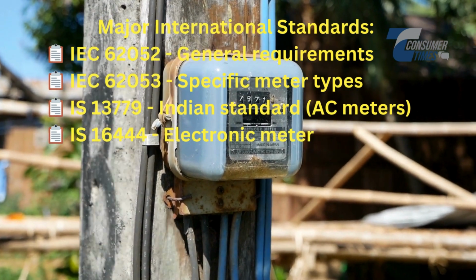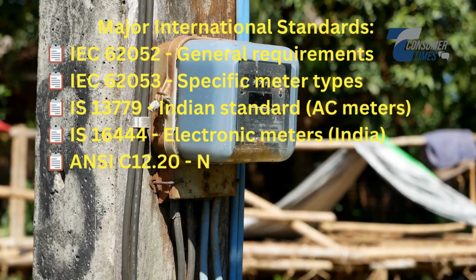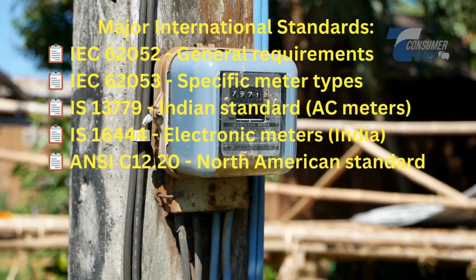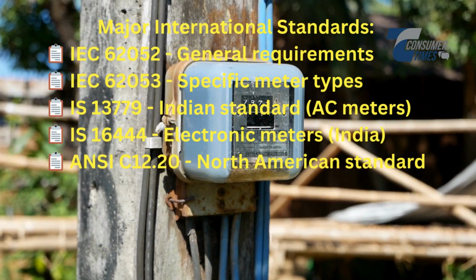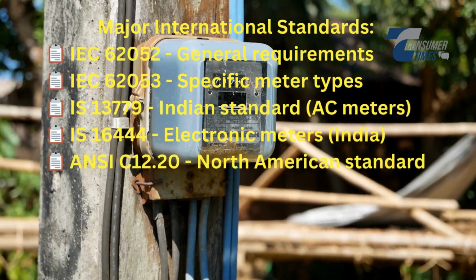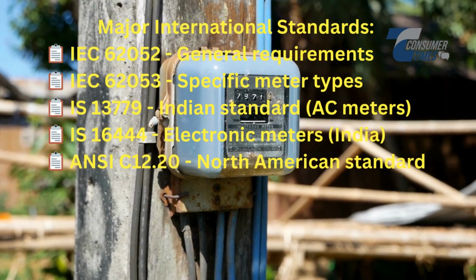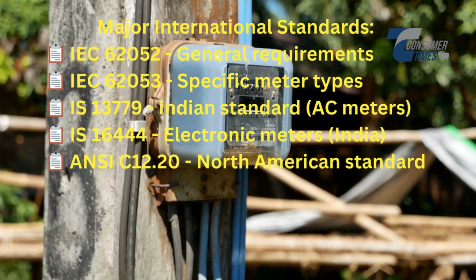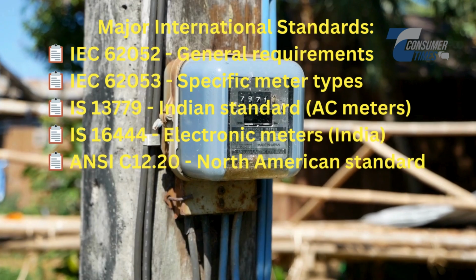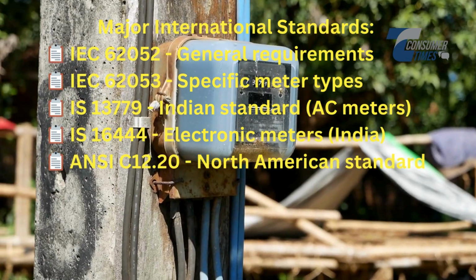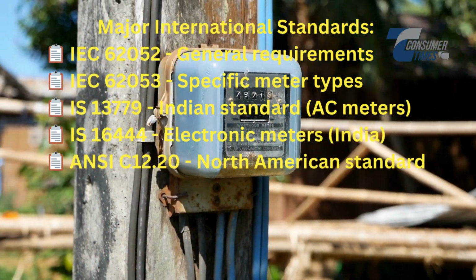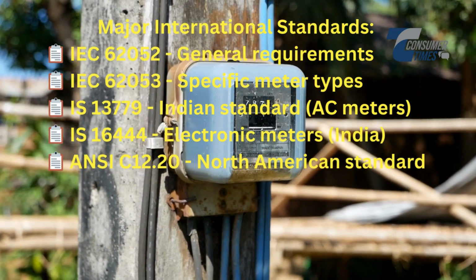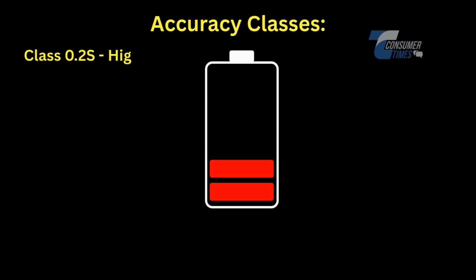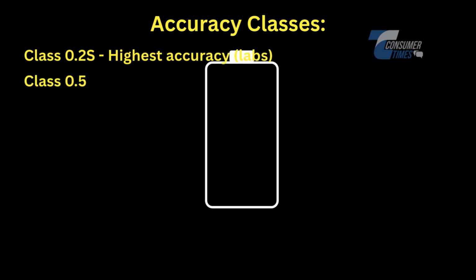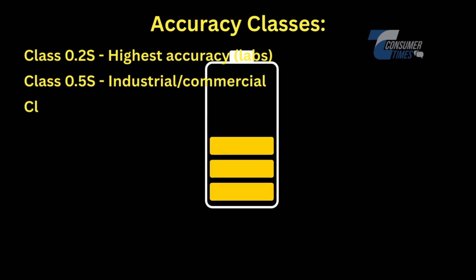Energy meters worldwide are governed by strict international standards to ensure uniformity, accuracy, and consumer protection. The most widely recognized standards come from the International Electrotechnical Commission, or IEC. The primary standards for energy meters are IEC 62052 and the IEC 62053 series. IEC 62052 provides the general requirements for electricity metering equipment, covering aspects like terminology, testing methods, and performance specifications.